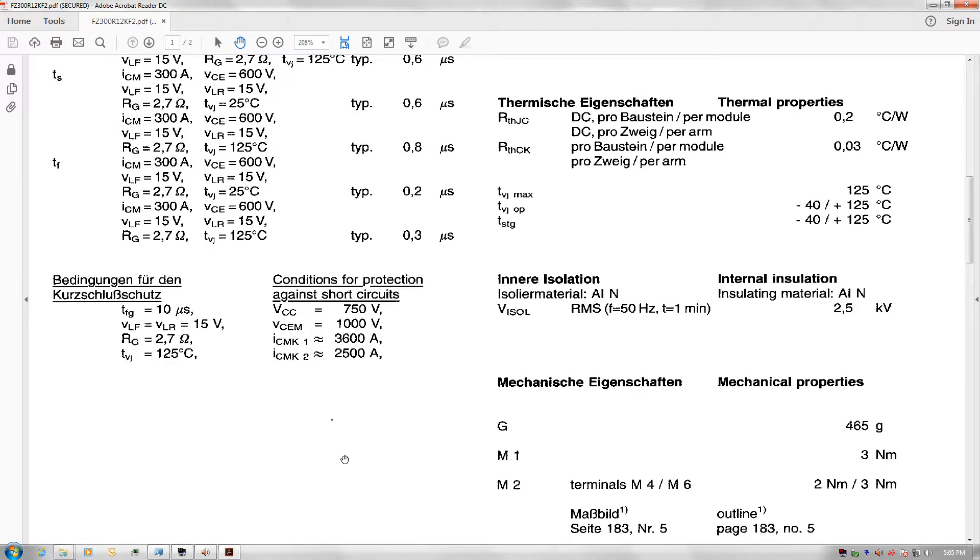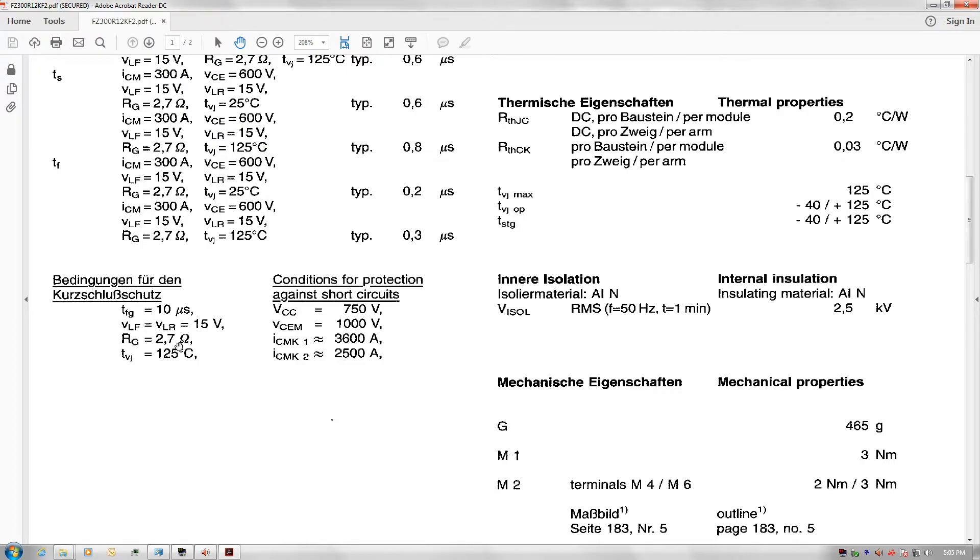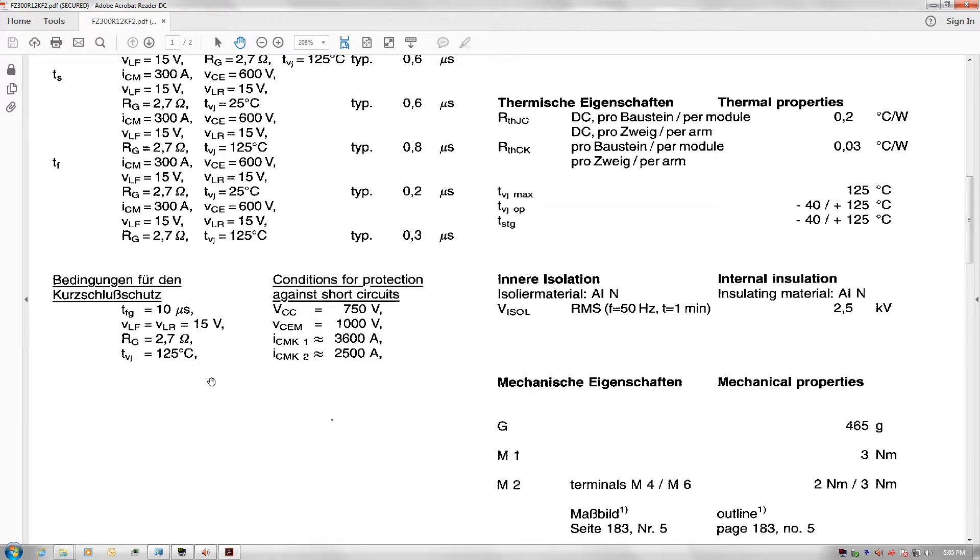You'll notice in this part of the datasheet, this line that reads conditions for protection against short circuits. They again specify a 2.7 ohm gate resistor. You can use a value lower than that, but if you do and the IGBT experiences a short circuit, the turnoff voltage spike will almost certainly destroy it. That's why they give you this minimum value.